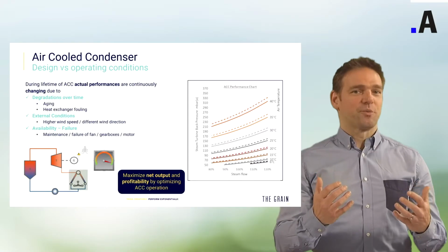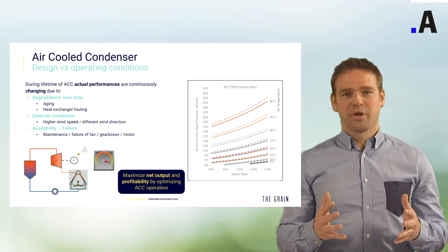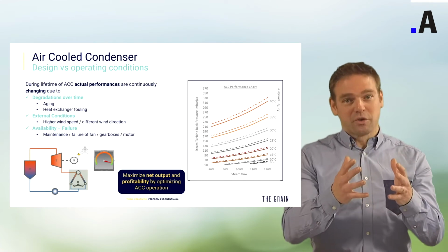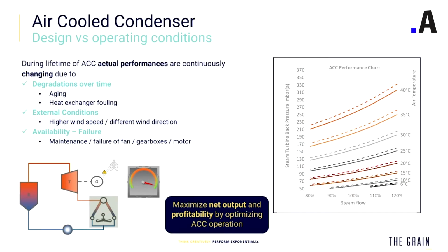Cooling performance is influenced by a number of variables, among which are steam flow, heat loads, and also ambient temperature. In the graph on the slide, you can see on the y-axis the back pressure and on the x-axis the steam flow for various temperatures. There you can see the relationships between both variables.